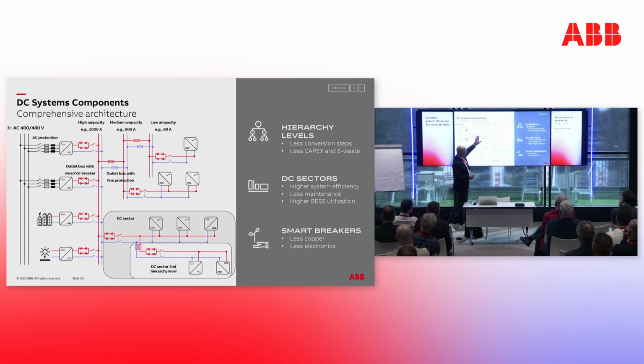The grid is split into hierarchies. This helps us design the circuit breakers and the needed connections between them. Importantly, loads are not always protected individually by a solid-state circuit breaker, since that could be expensive. Very often, the sector is protected by a solid-state circuit breaker, and inside the sector we use more traditional devices like fused switch disconnectors and so on.